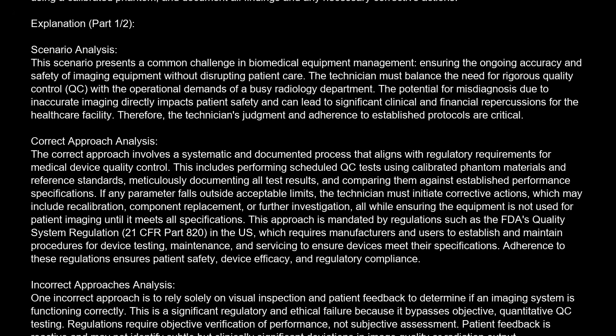The potential for misdiagnosis due to inaccurate imaging directly impacts patient safety and can lead to significant clinical and financial repercussions for the healthcare facility. Therefore, the technician's judgment and adherence to established protocols are critical. Correct approach analysis. The correct approach involves a systematic and documented process that aligns with regulatory requirements for medical device quality control. This includes performing scheduled QC tests using calibrated phantom materials and reference standards, meticulously documenting all test results, and comparing them against established performance specifications.